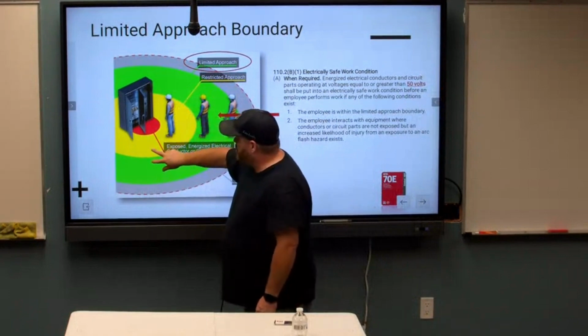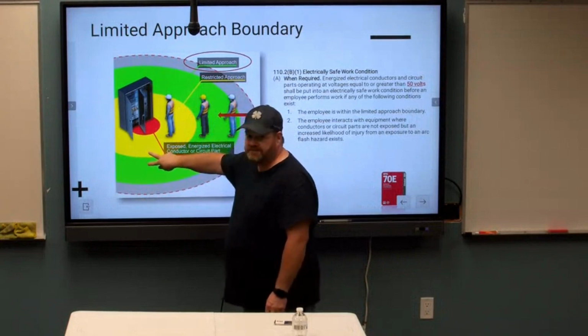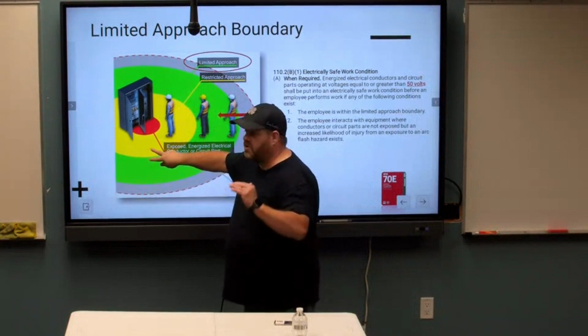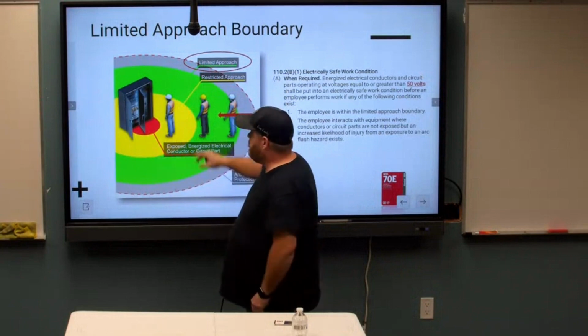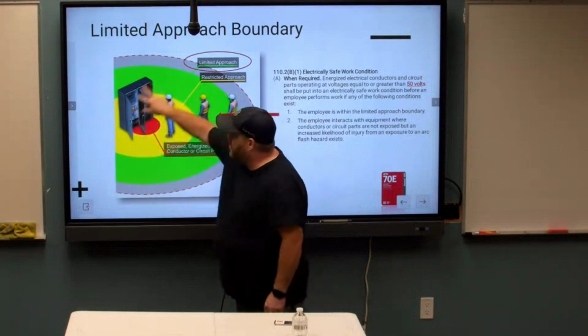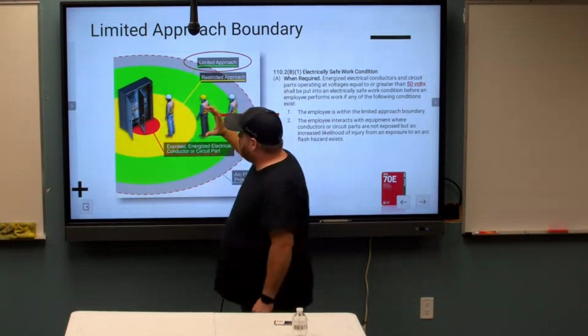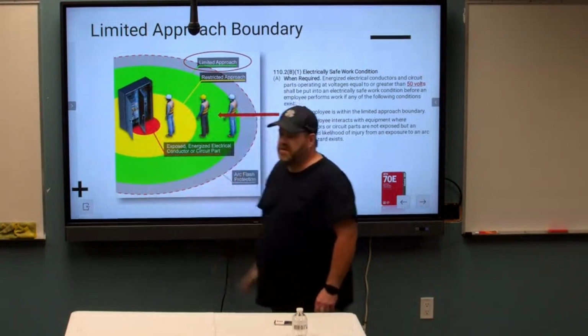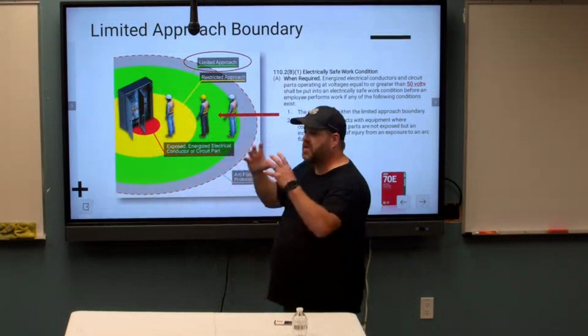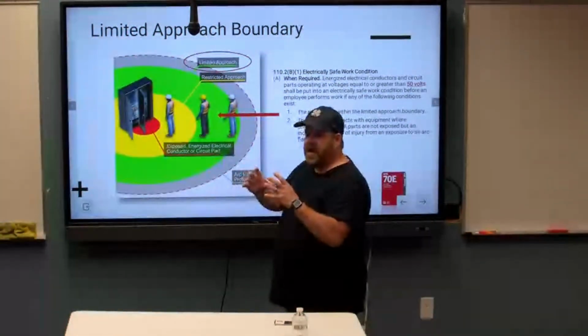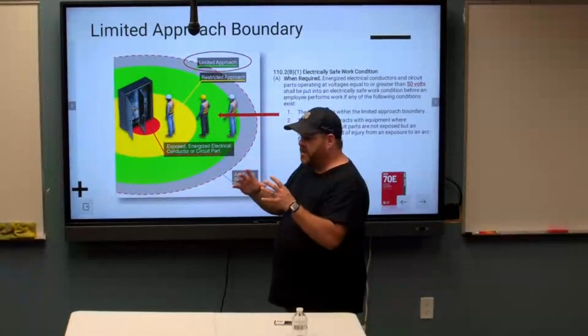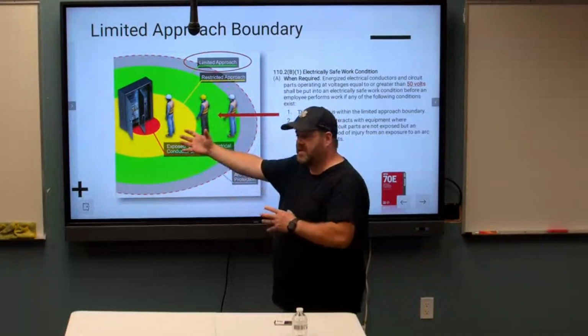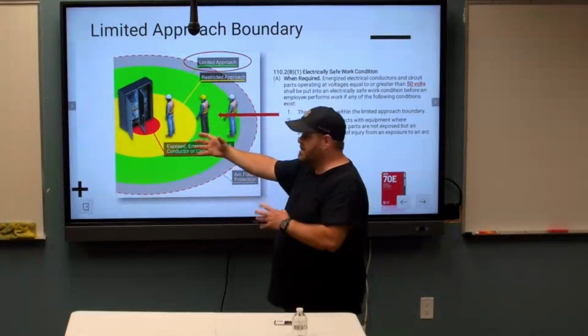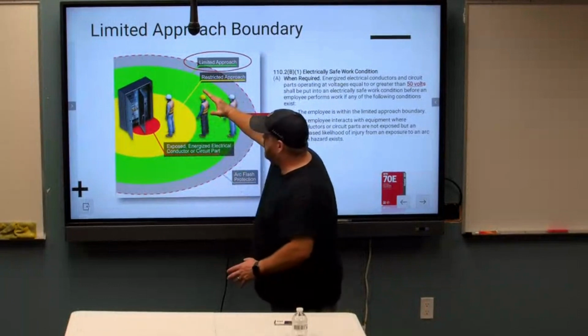Take note that your limited and your restricted approach boundaries are for shock protection, not arc flash. Just the electrical shock that we talked about earlier, okay? So let's say you have your exposed energized circuit parts right here. The closest boundary to those exposed energized parts is your restricted approach boundary. We're not allowed to have anything conductive in that boundary. We're not even allowed to be in that boundary unless we're insulated or the equipment's insulated. Make sense? Then the outer boundary, shock boundary, this green one.